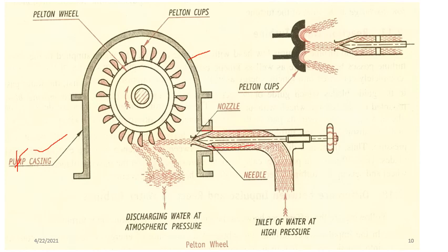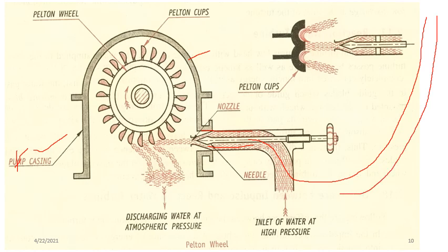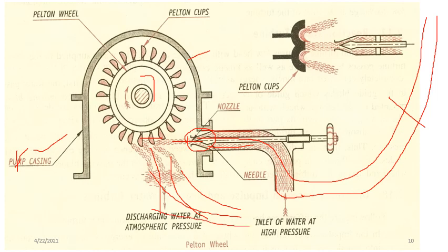The water enters this turbine from the reservoir. It comes through a pipeline which we call the penstock, and then it enters into the turbine. At the entrance there will be a nozzle, which is a reduction in the diameter. Then a high velocity jet comes out of the nozzle, strikes the blades, and makes it rotate in this direction. Okay. After striking, the water passes out of the turbine through a tail race. This is called the tail race, the exit of the turbine.